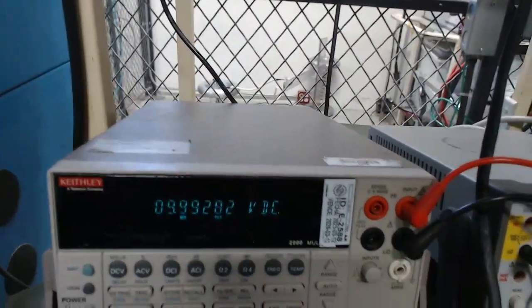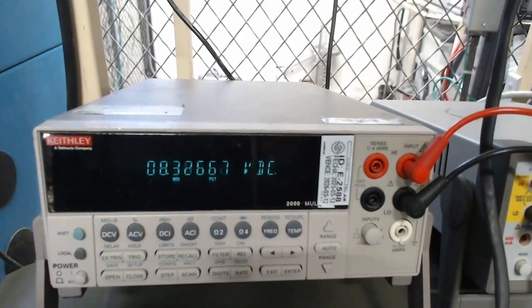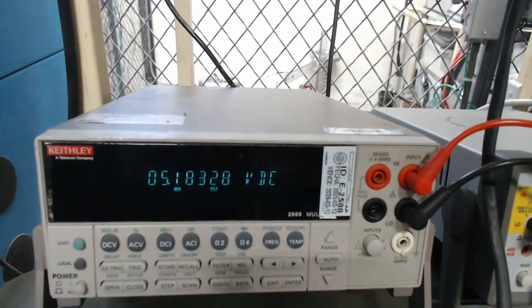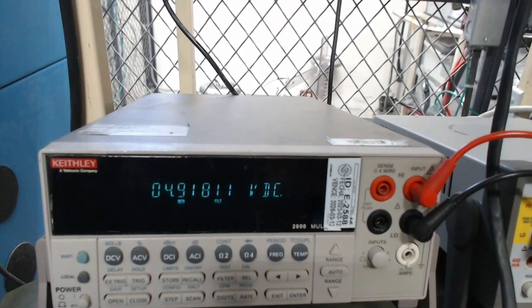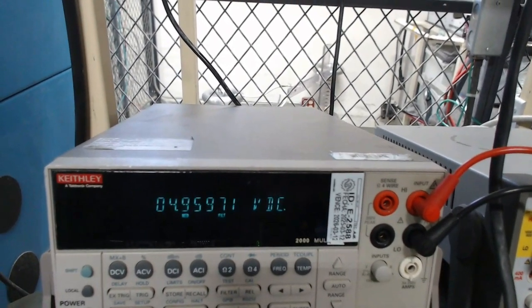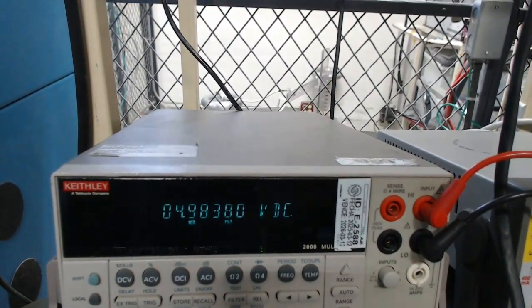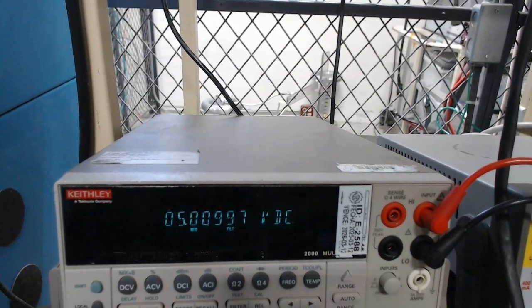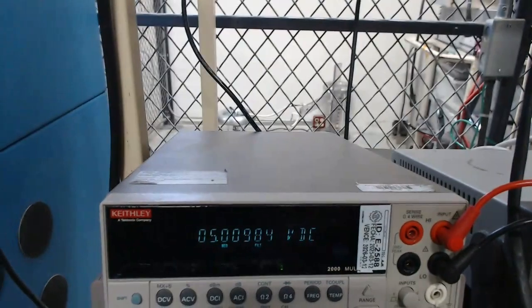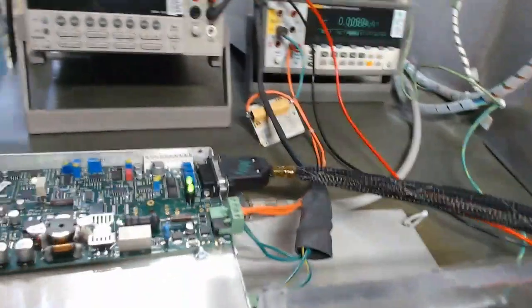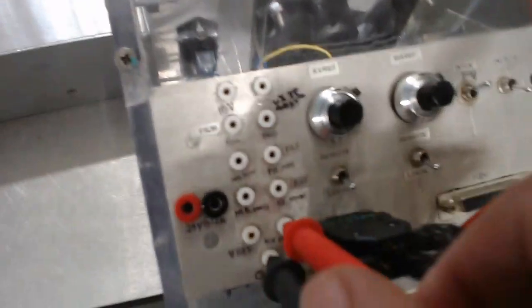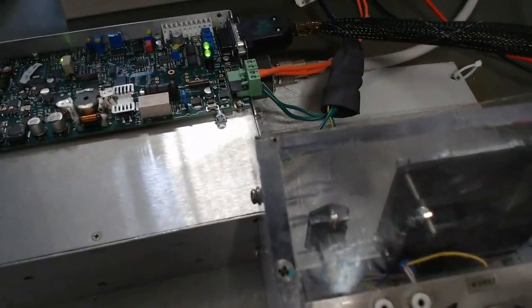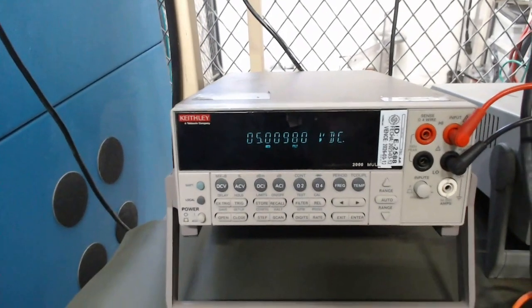Programming voltage will then be lowered to half scale, which is 5 volts of programming with a tolerance of plus or minus 50 millivolts. Once the value achieved is as centered as possible, the voltage monitor test point will be measured, where we are confirming that the monitor signal is 5.009 volts at 25.11 kilovolts, both of which are under specification. Value is then registered to the test data sheet.